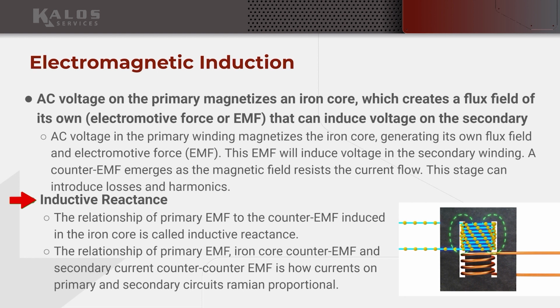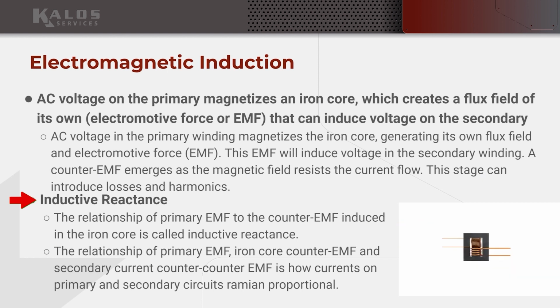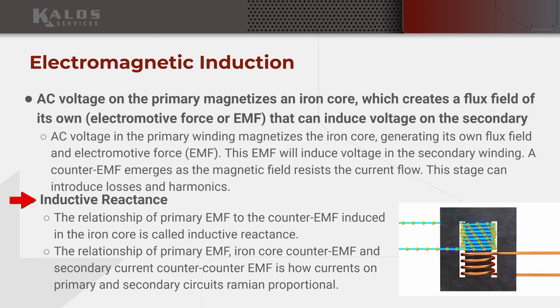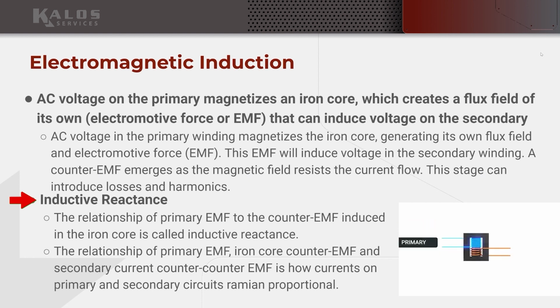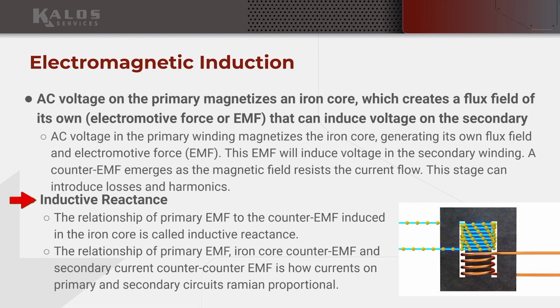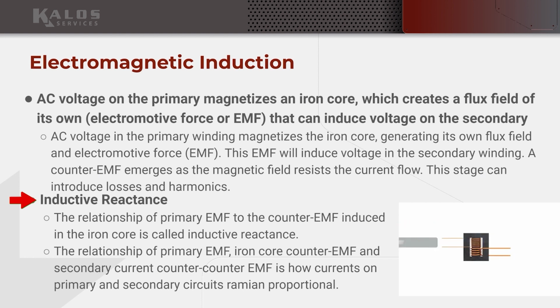Have any of you taken a voltage meter or continuity tester and put it across the transformer coil, primary or secondary? You test before turning on the transformer, to make sure you don't have short circuits. You read from A to B, you ring out very low resistance, almost zero. B to C, same thing, no resistance. That's really head scratching.